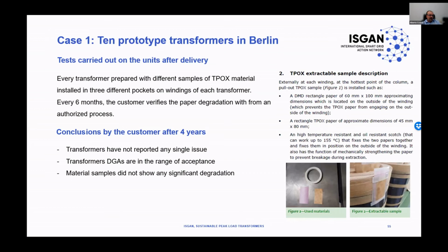Following this method, every 6 months the utility has the opportunity to inspect the windings, to inspect the active part of the transformer, and verify if there is a decomposition of the insulation material. After 4 years, we can say that at the moment there is no decomposition. The material is still perfect, and the DGAs are still showing perfect values compared with the starting value.